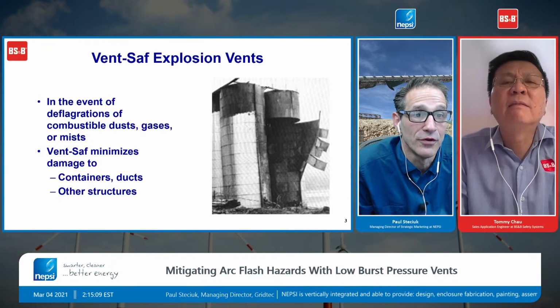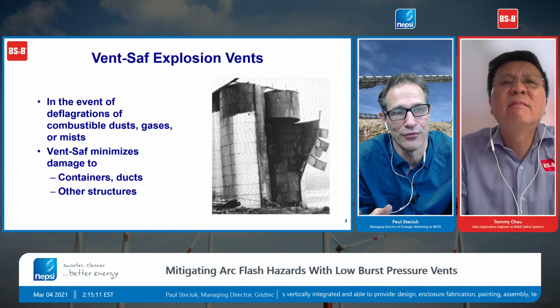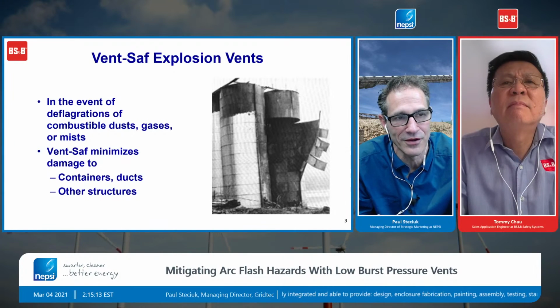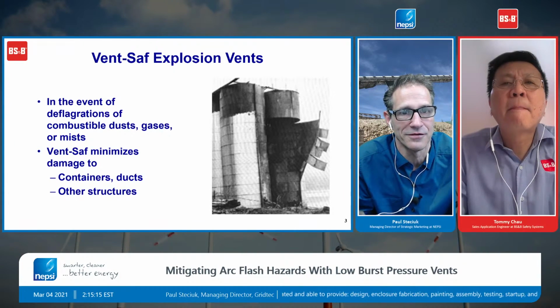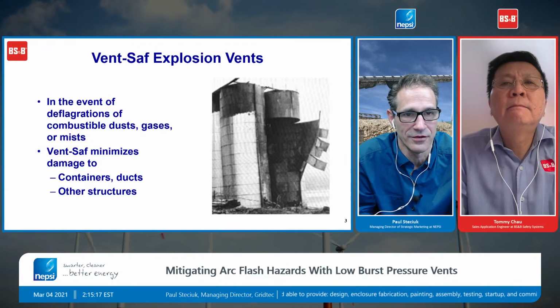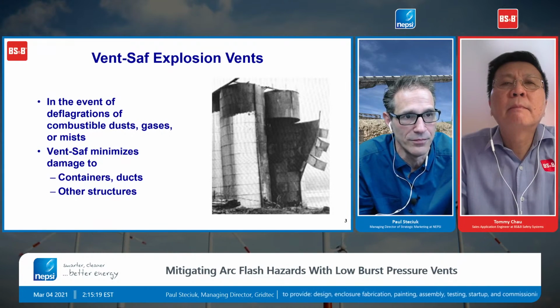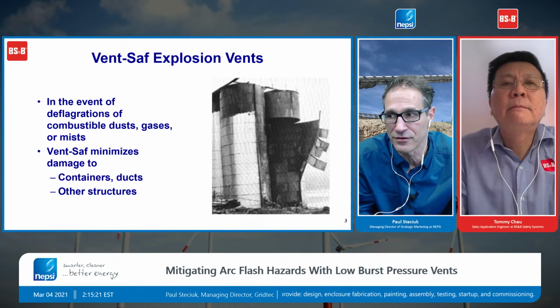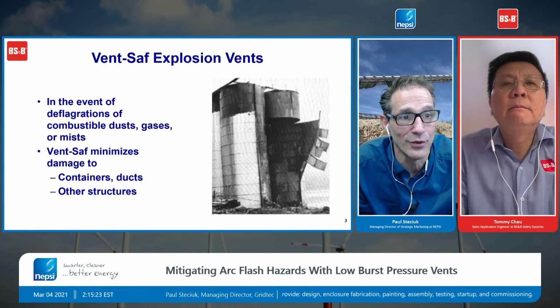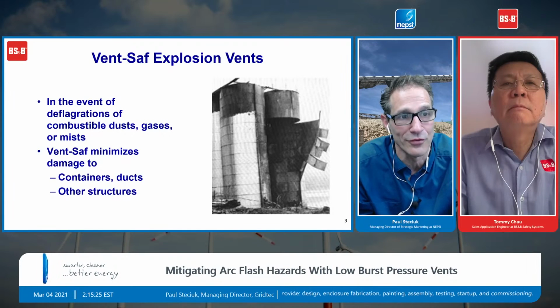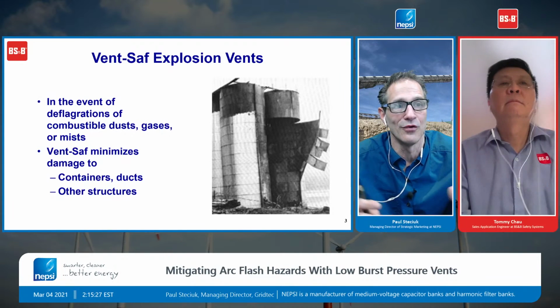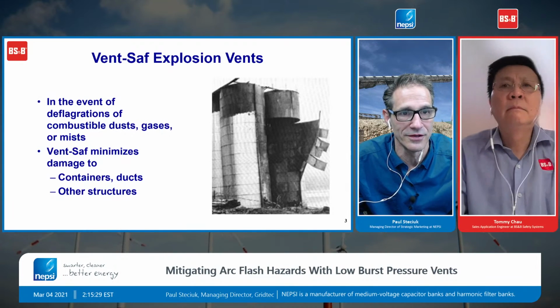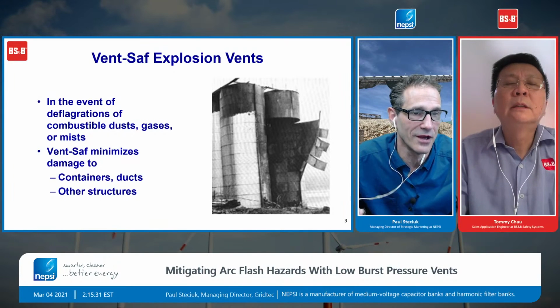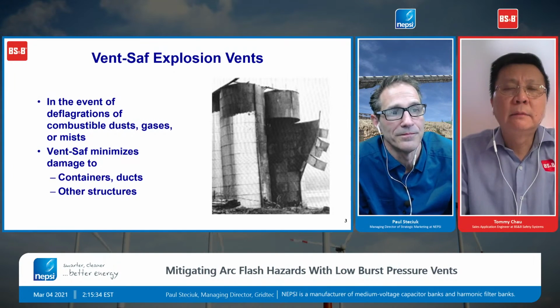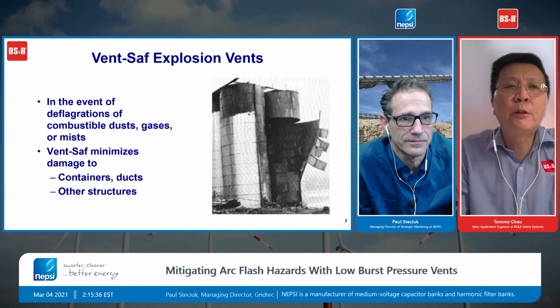Correct. So if you don't give a place for the pressure to go, an exhaust area, what you get is the whole thing fails. The whole building might fail. If it's a building, if it's a silo, the whole silo fails. And if it's a piece of switchgear or a metal enclosed cap bank or a filter bank, then the whole enclosure will get damaged and fail. And that's kind of what these things do. Correct. It's a low pressure device.